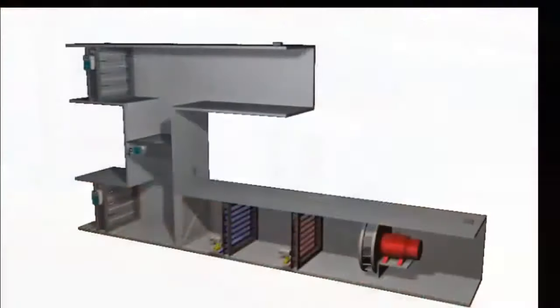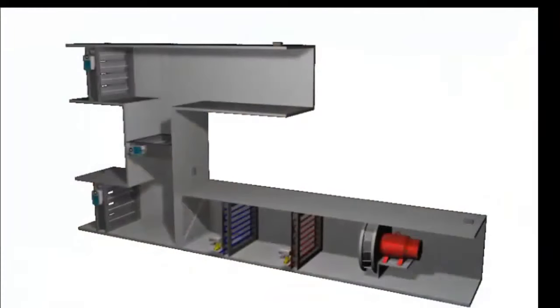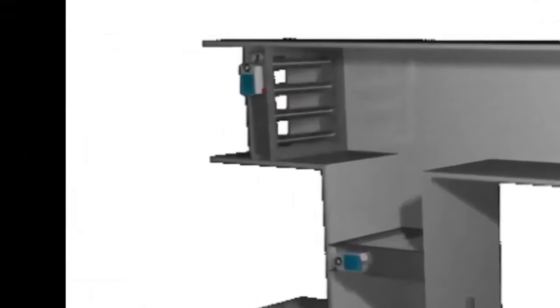What are the characteristics of a typical Air Handling Unit? First, in a basic model we have two ducts, one for supply and one for return air. Second, the AHU has a mesh to prevent entry of objects. Third, at the supply and return input we have some dampers. Fourth, the dampers are multiple sheets of metal that can rotate, and can be closed to prevent air from entering or leaving the AHU.